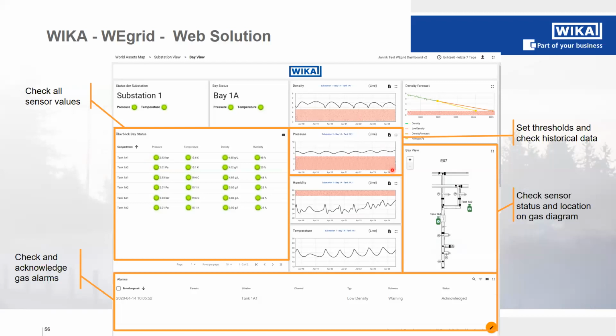On the bottom side, you have the alarms that have been raised. For example, if a threshold has been crossed, you can see here this warning, and that this warning has gone to an SMS or email contact. And on the right side, you have an excerpt from the GIS layout, and you can check the location of the sensors, these green boxes here. So you will always be able to see directly where inside the GIS your issue might be, if you have one.